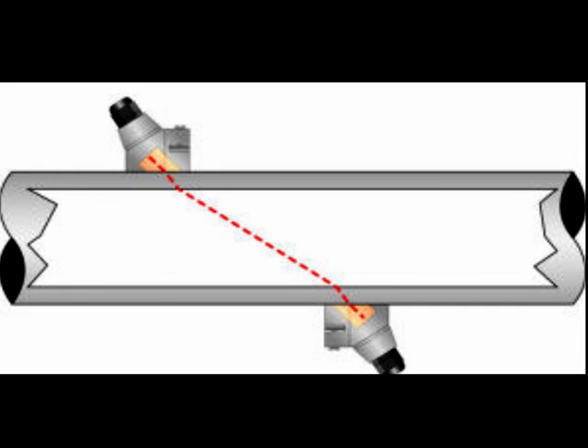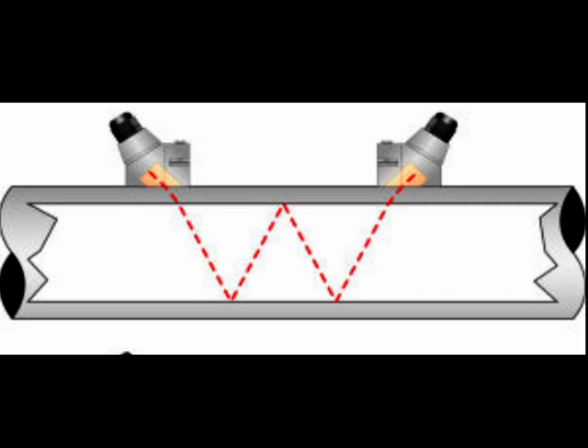Also because of the mechanical considerations in mounting the transducers, we can extend the path of the ultrasonic signal. A single traverse, a double traverse, and finally a four traverse.